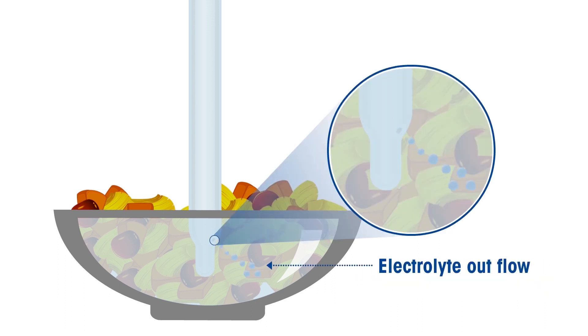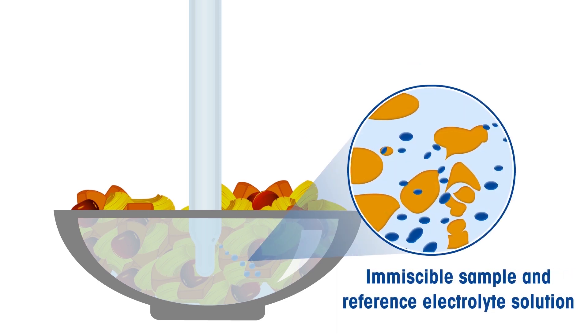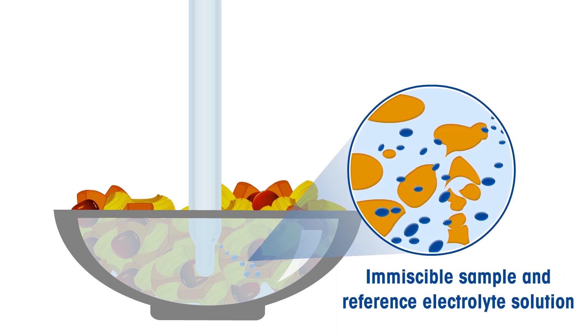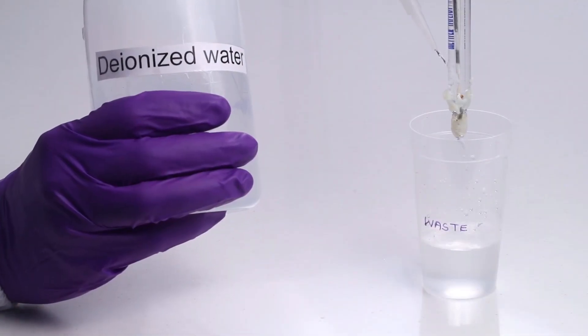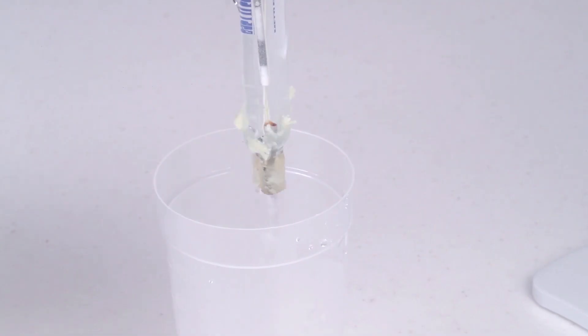High fat content from the sample does not mix readily with aqueous reference electrolyte, which results in high response time. After the measurement, it is difficult to clean the sticky residue of food sample from pH electrode glass membrane.